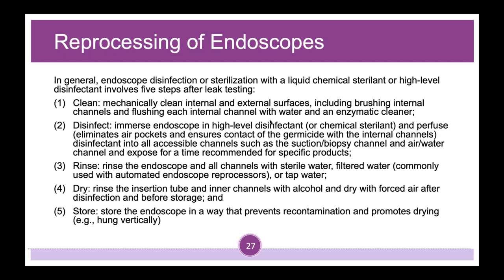So in general, endoscope disinfection or sterilization with a liquid chemical sterilant or high-level disinfection involves 5 steps after you do your leak testing. First, clean: mechanically clean internal and external surfaces, including brushing internal channels and flushing each channel with water and an enzymatic cleaner.